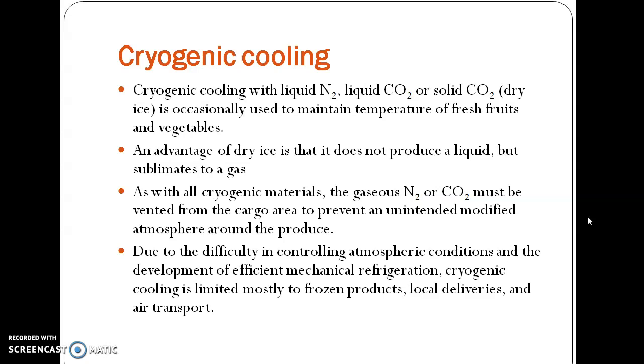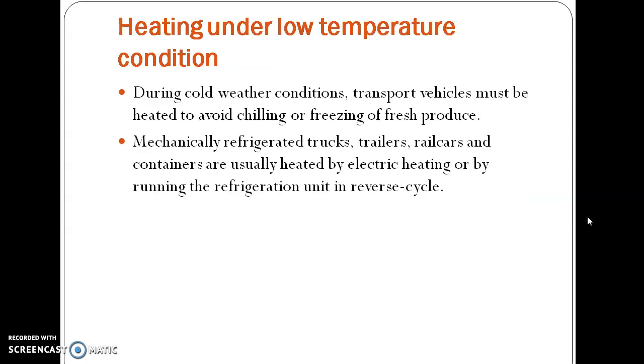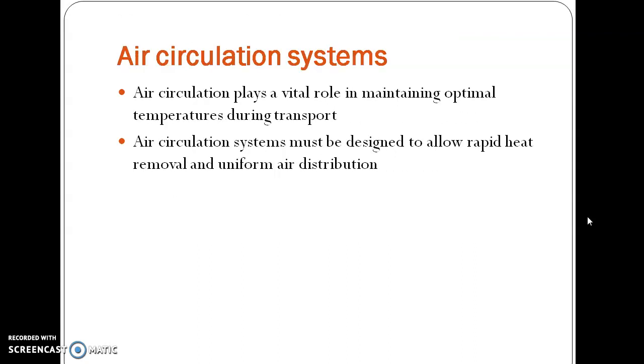The advantage of dry ice is that it does not produce liquid but sublimates directly to carbon dioxide gas. When using cryogenic materials, the gases such as carbon dioxide and nitrogen must be vented out of the cargo and should not create a modified atmosphere around the produce. Sometimes, when environmental temperatures are very low, heating is needed to raise the temperature of the trailer to avoid chilling and freezing of the produce. The air circulation system of the trailer should be effective enough to remove heat from the trailer and uniformly distribute air within it.